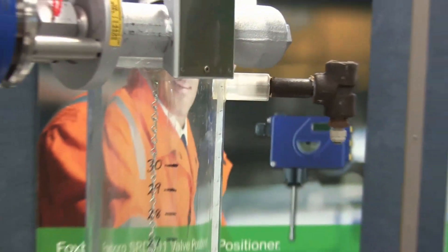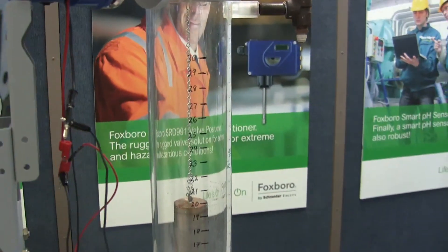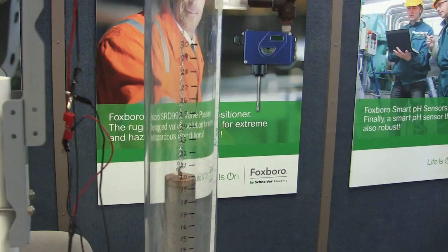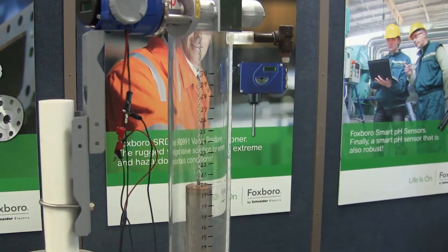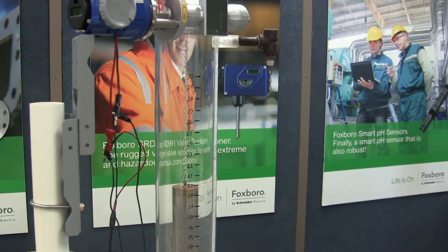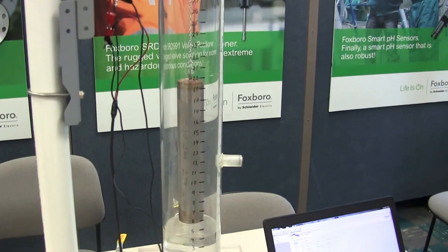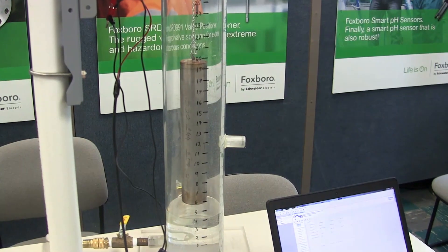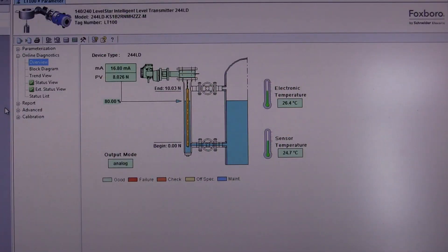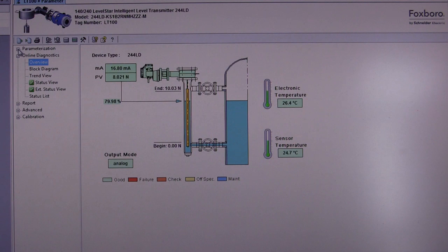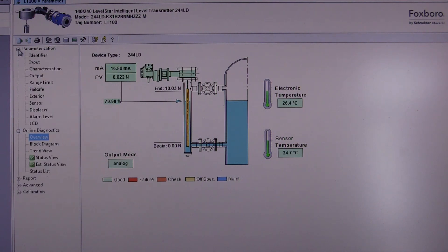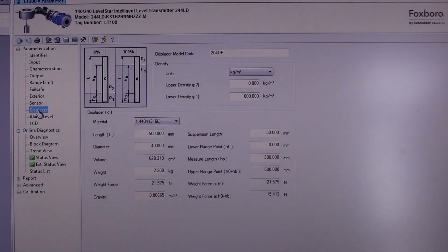Before performing the calibration function, be sure that the displacer element is at an empty tank condition. Once you have connected to the transmitter using PACTware, open up the parameterization tab and go right to the selection labeled displacer.